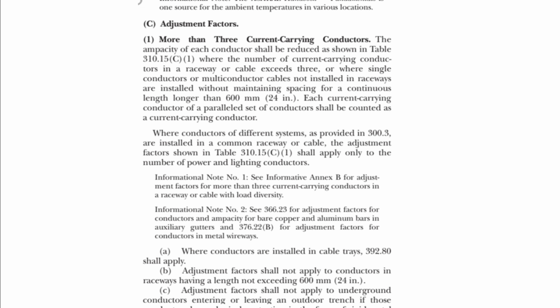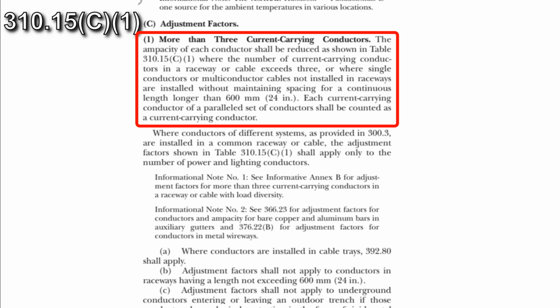It's not that easy, because 310.15(C)(1) requires additional adjustment factors if there's more than 3 current carrying conductors in the conduit. 310.15(C)(1), Adjustment factors. More than 3 current carrying conductors. The ampacity of each conductor shall be reduced as shown in Table 310.15(C)(1), where the number of current carrying conductors in a raceway or cable exceeds 3, or where single conductors or multi-conductor cables not installed in raceways are installed without maintaining spacing for a continuous length longer than 24 inches. Each current carrying conductor of a paralleled set of conductors shall be counted as a current carrying conductor.